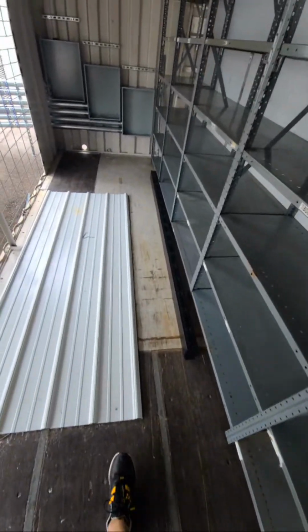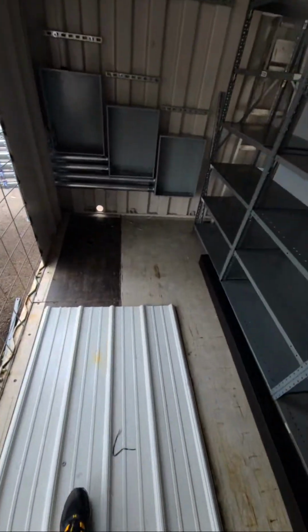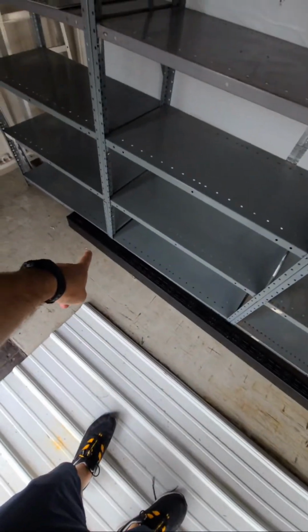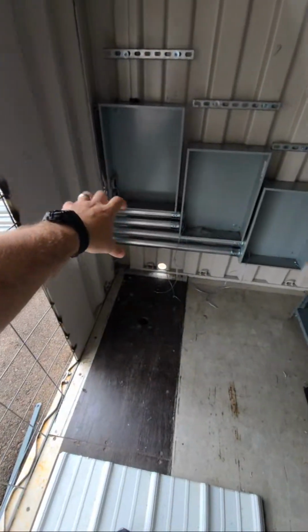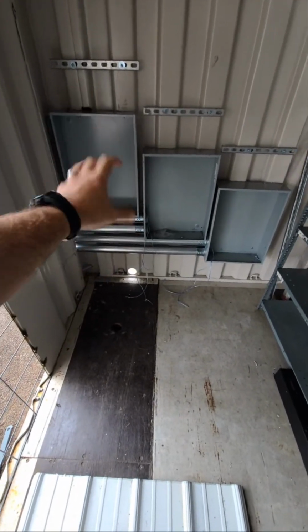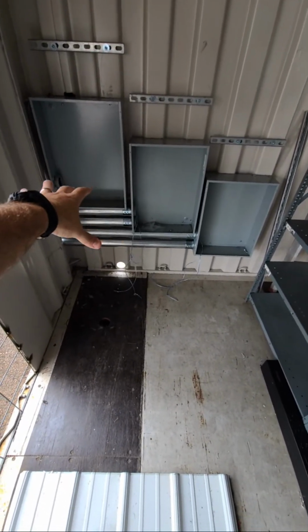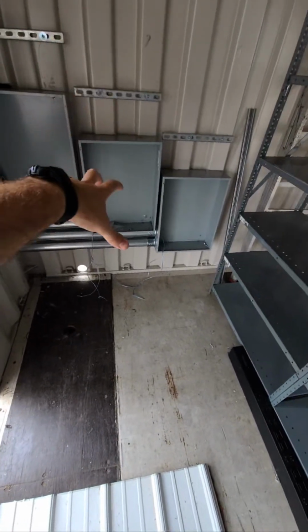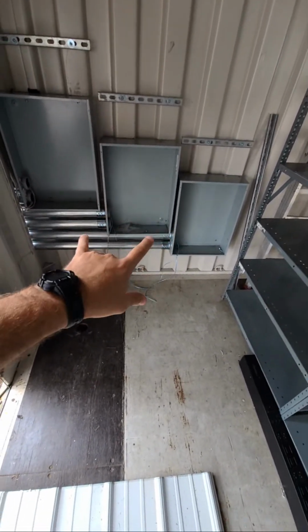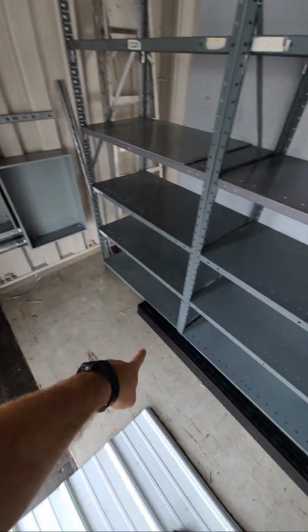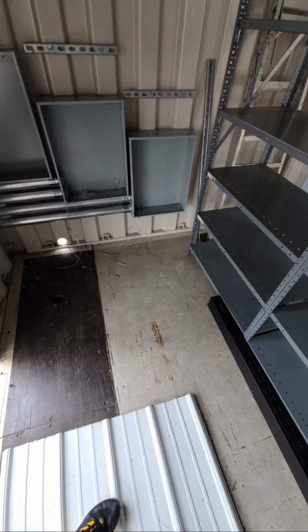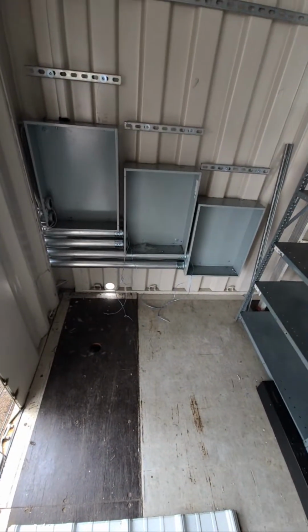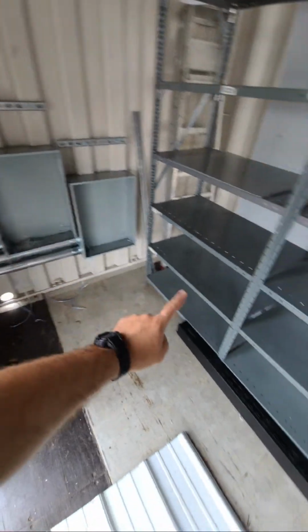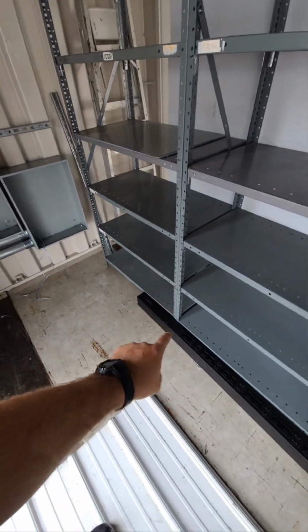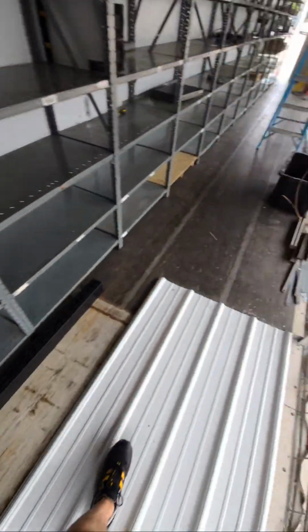The cables to the PDUs are what size? So the way you do it is, these PDUs are 277 volt. We get 480 coming in, each leg is 277. I'm not the electrician here, but the idea is it comes in, it's split up into 13 different 277 legs that then go to your PDUs. So I don't know what size it is, that's where the electrician, my partner, comes in. But it's going to be 125 amp 277 for each PDU, so whatever size cable you need.